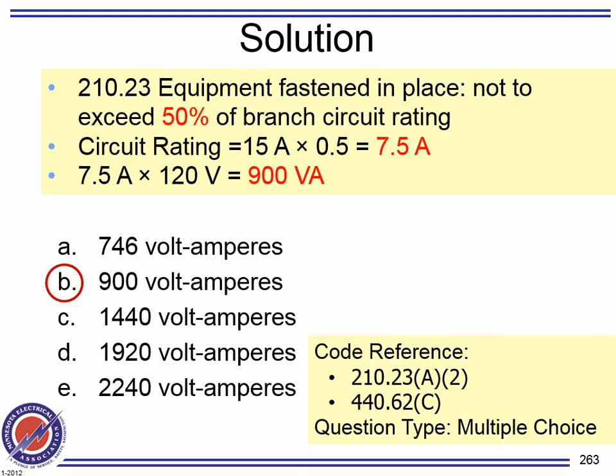So there you go. So my circuit is not 20, it's a 15 amp. I have to cut it by half because it says if the equipment is shared, you cut it by half. That gets you this amount multiplied by the voltage, and that will get you 900 volt amps. So my AC unit must not be more than 900 volt amps, or I have to put it on a dedicated circuit. I think this is the one that can get you a dedicated circuit, or one of them.